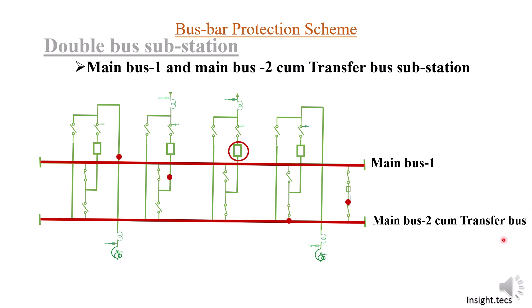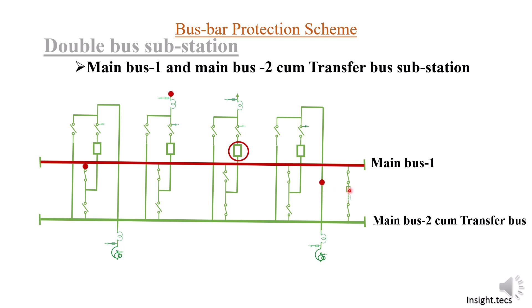To use the transfer bus, first turn off the circuit breaker and connect the bus coupler circuit breaker, connecting all equipments to a single bus. All equipments are connected to bus one. Then close the separate transfer isolator, open the two selector isolators for that feeder, and now the power will be transferred to bus two. Bus two is now working as main bus cum transfer bus.